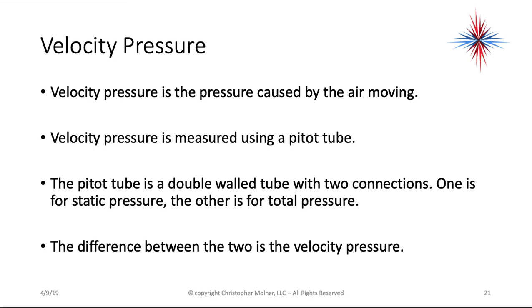Velocity pressure is another pressure we discuss. Velocity pressure is the pressure caused by air moving, and it is measured using a pitot tube. The pitot tube is a double-wall tube with two connections — one gives you a static pressure reading and the other is for total pressure. The difference between the static pressure and the total pressure is your velocity pressure. Velocity pressure is strictly the pressure of the air moving in the ductwork, and static pressure cannot be included in that reading — that's why we subtract it out.